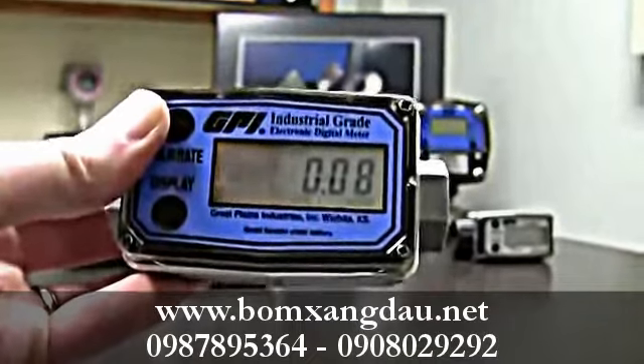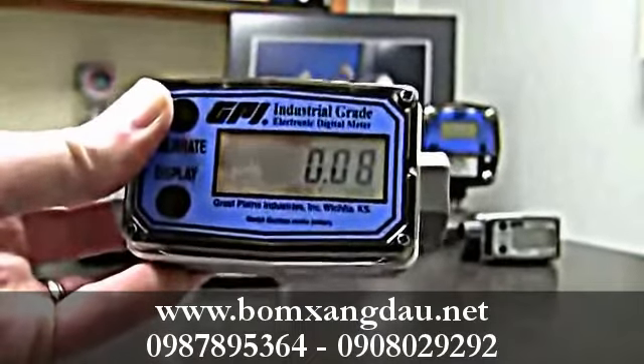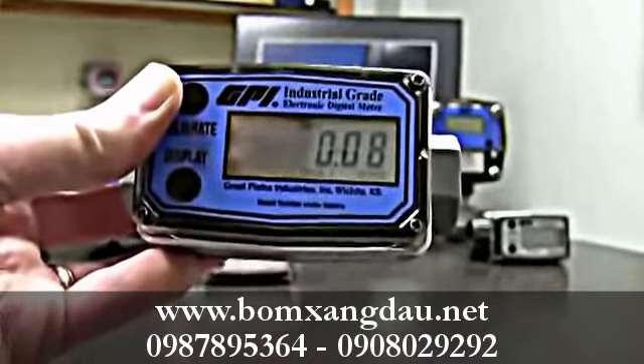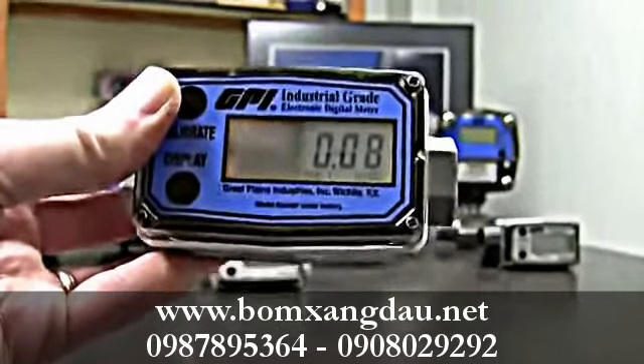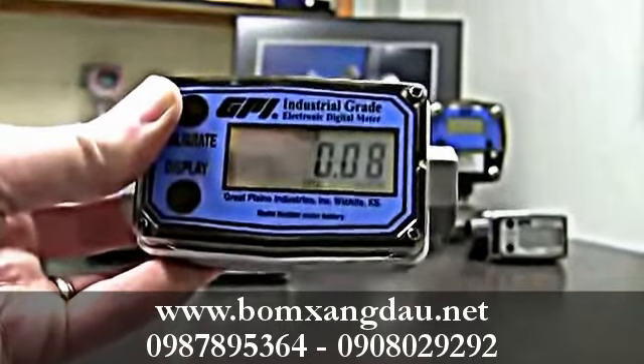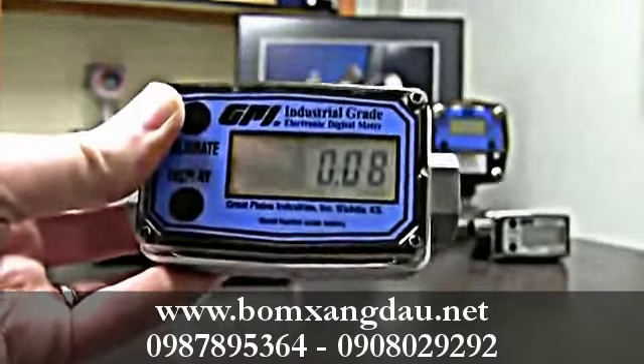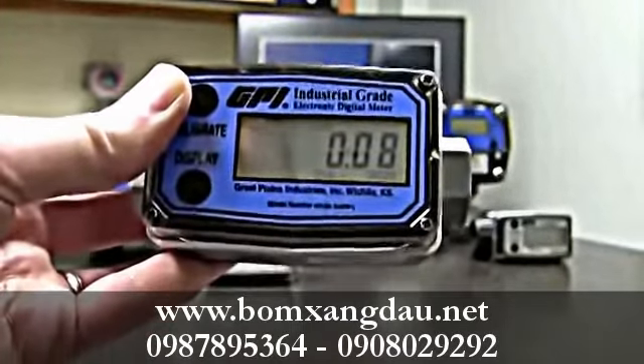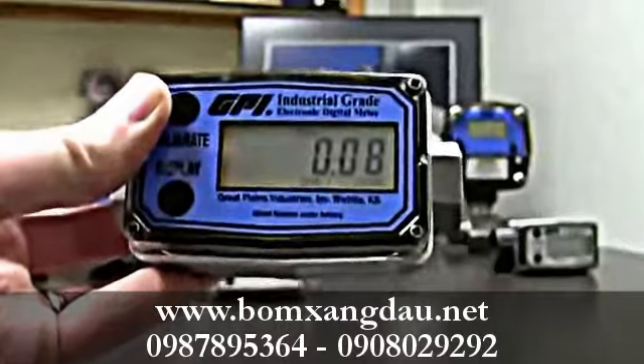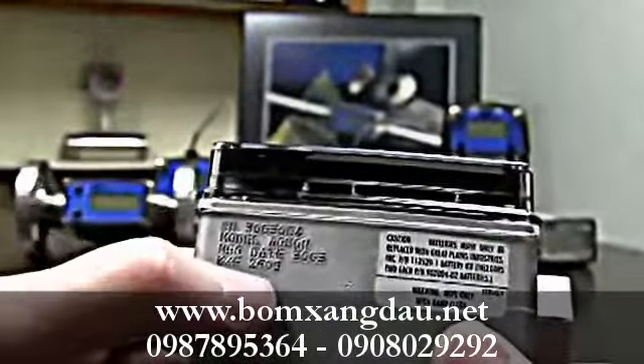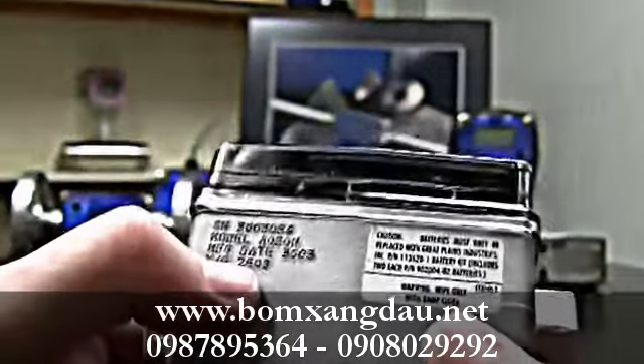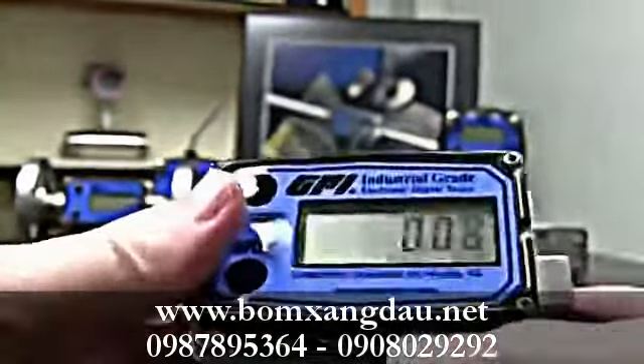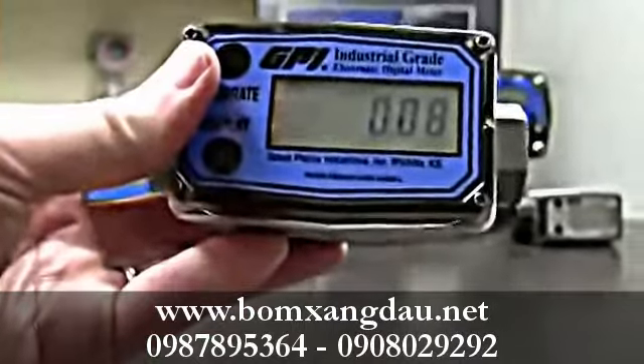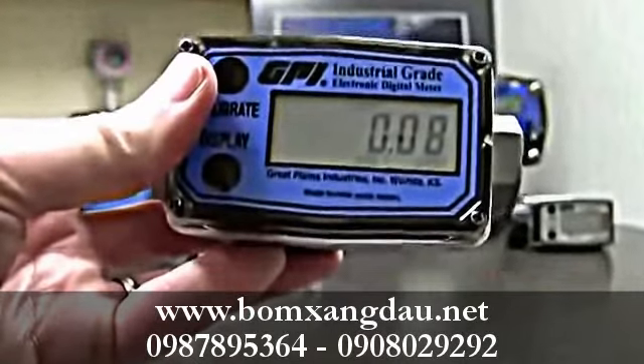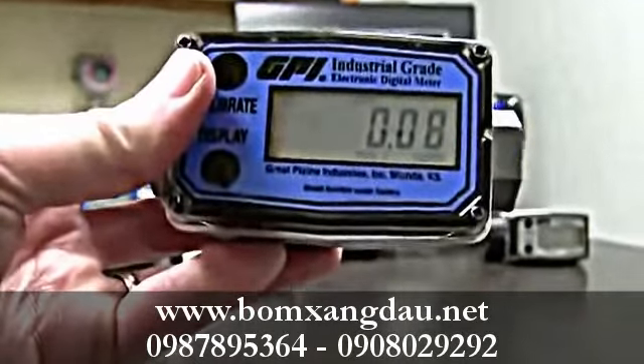Now first of all, why would you want to change a calibration? These come calibrated to water. Let's say you were running something a little bit thicker through it, like antifreeze. So you're putting antifreeze through this meter. It's a little bit thicker, so it's going to make the turbine inside turn a little bit slower. This meter has the K-factor printed right on it, which this one happens to be 2,609 pulses per gallon. Well, that is for water. If you're putting the antifreeze through it, which is a little bit thicker, it wouldn't be that many pulses.